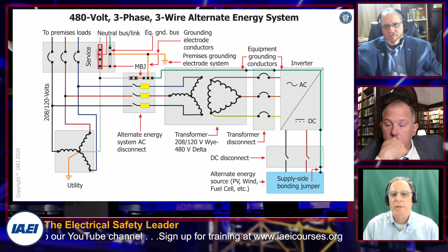And if you go 2 more slides, I think it is. Before you do that, though, that transformer on the right, is it going from low voltage on the AC inverter side to a higher voltage, or is it vice versa? This is going the other way. This is 480 volt delta to 208/120Y. Okay. So I'm actually taking voltage down to get into the service because the service is 208. Gotcha. If the service is 480, I could do a direct connection.